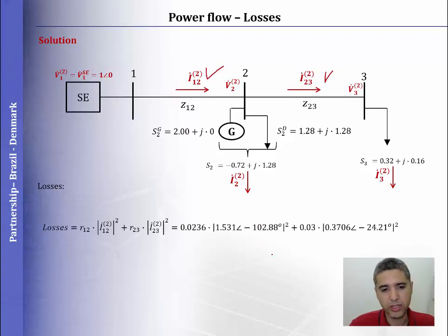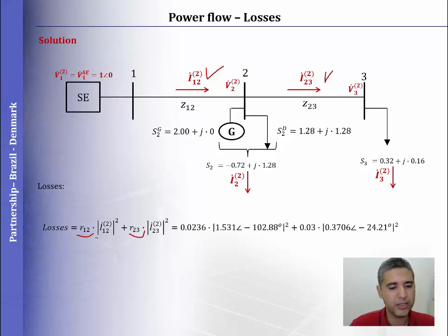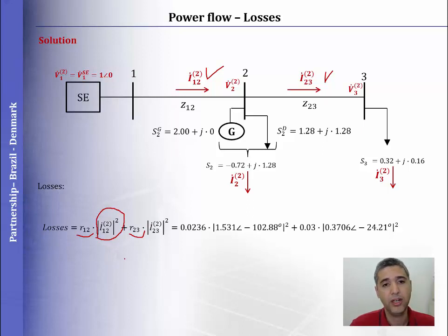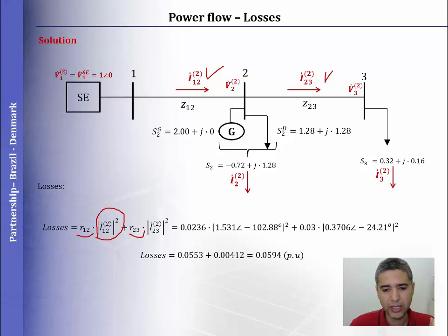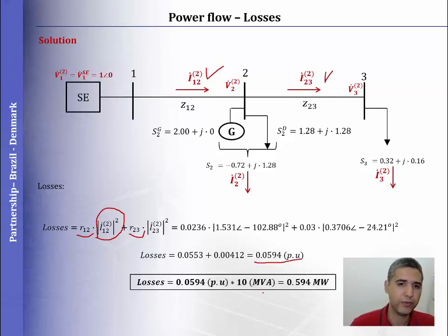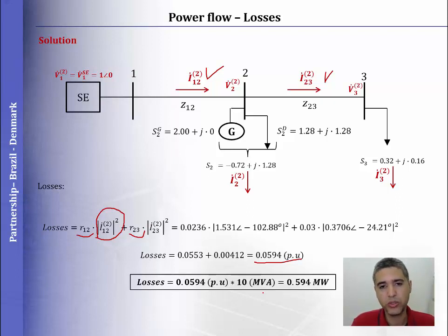Since we have the voltage and the current, we can compute the losses by multiplying the resistance of each line by the square of the current in that line. This gives us the value in per unit. If you want the value in megawatts, you need to multiply by the base power.